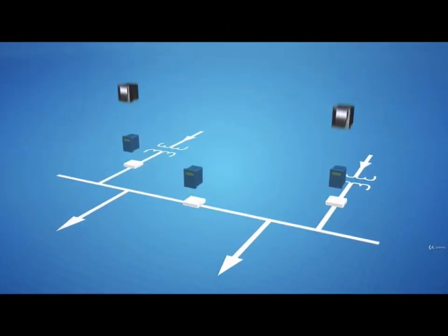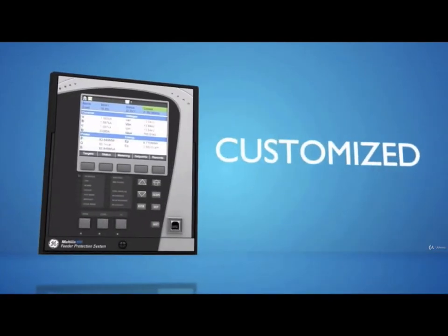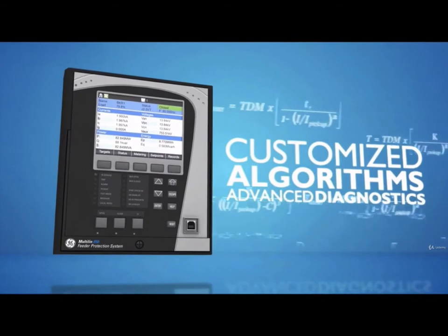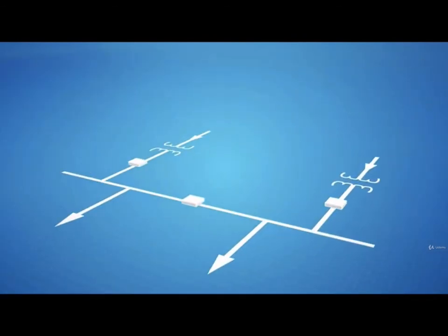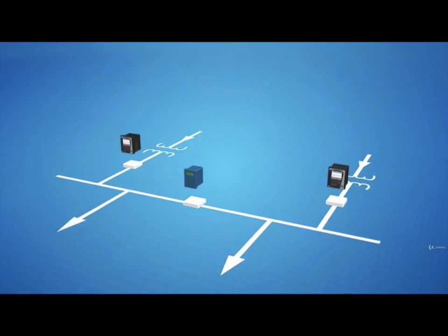Some recent IEDs are designed to support the IEC 61850 standard for substation automation, which provides interoperability and advanced communications capabilities. In utilities and industrial electrical power transmission and distribution systems, a digital protective relay is a computer-based system with software-based protection algorithms for the detection of electrical faults. Such relays are also termed microprocessor type protective relays. They are functional replacements for the electromechanical protective type relays and may include many protection functions in one unit, as well as providing metering, communications, and self-testing functions.